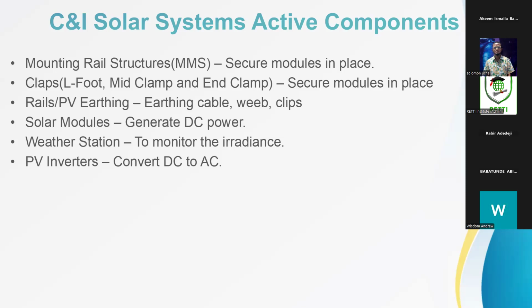It varies from manufacturer to manufacturer, but there is a rule that guides almost everybody. It's what we call the DC to AC ratio. For your DC to AC ratio, 1.2 is good. Don't go beyond. Some people go 1.31, but I always advise you don't go beyond 1.2. The essence is that the more you go, the more clipping you have. Once your PV is producing more than what the PV inverter can take, you just clip it and you are just wasting it. So a 1.2 DC to AC ratio is fine.